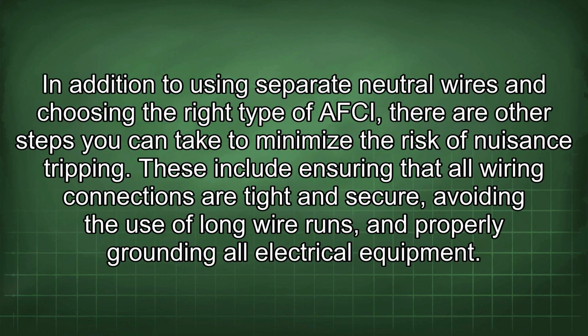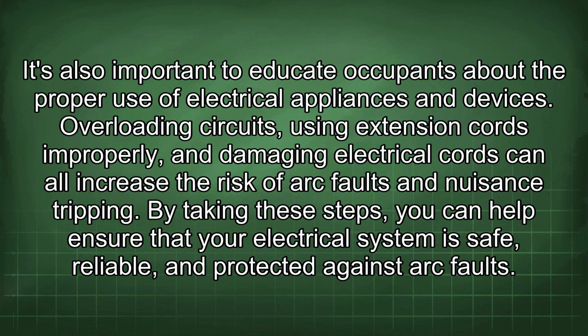In addition to using separate neutral wires and choosing the right type of AFCI, there are other steps you can take to minimize the risk of nuisance tripping. These include ensuring that all wiring connections are tight and secure, avoiding the use of long wire runs, and properly grounding all electrical equipment. It's also important to educate occupants about the proper use of electrical appliances and devices. Overloading circuits, using extension cords improperly, and damaging electrical cords can all increase the risk of arc faults and nuisance tripping.